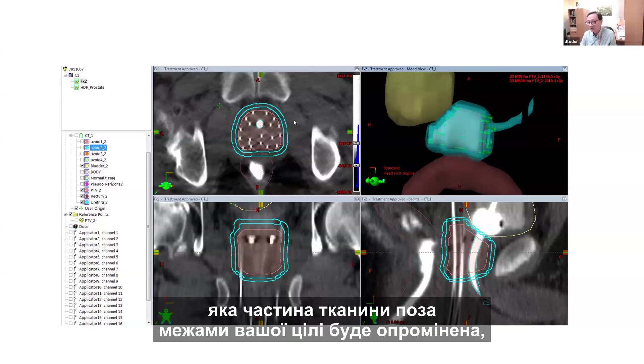What the optimizer is going to occasionally do, depending on the placement of your applicators, is that there is no limit to how much of the tissue outside of your target is going to be irradiated, okay? So what you would like to do is convey to the optimizer, if you were able to tell it in natural language, oh, by the way, I want this level of coverage, but make sure that it's conformal. So essentially, it's the conformity of the dose to the target that you are enforcing by adding to your structures this ring structure, okay?